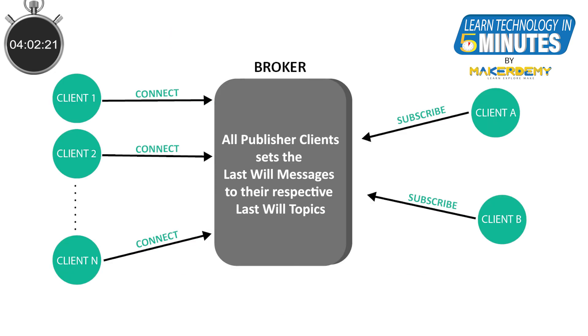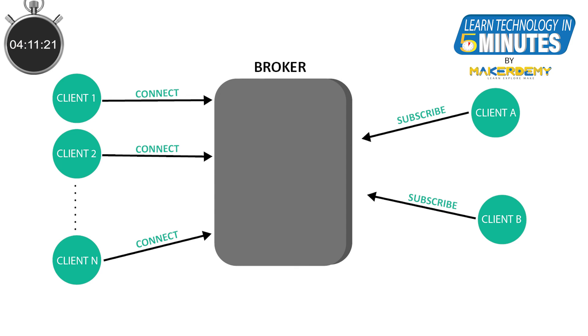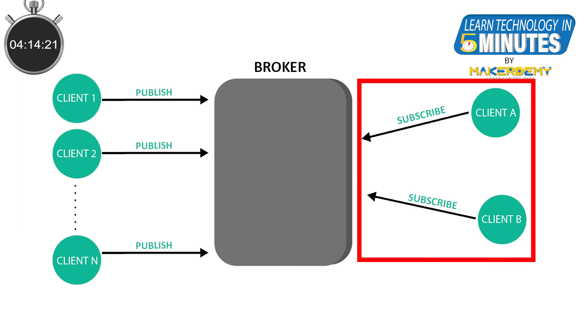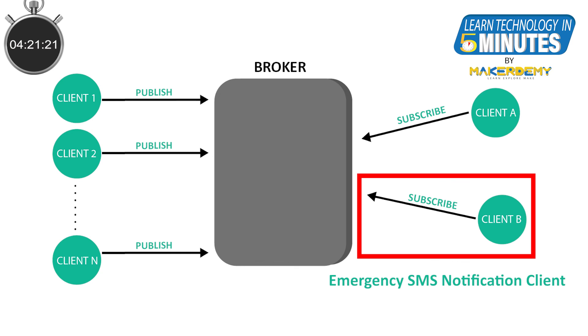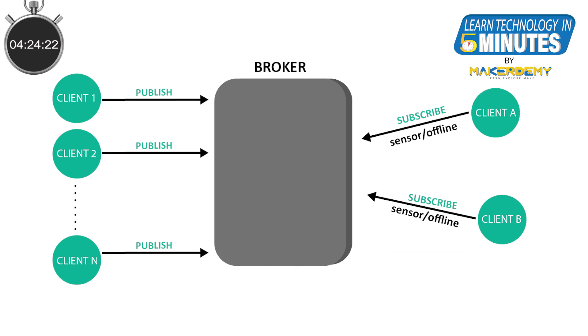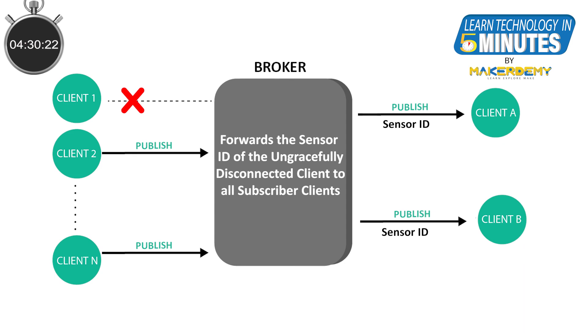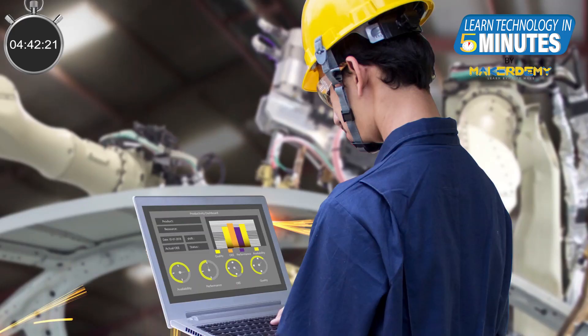This issue could have been easily solved if the system had used the Last Will and Testament feature of MQTT. All the sensor nodes, on their first connection to the broker, will set the last will message as their sensor ID to a topic called sensor/offline. Let's say we have two subscriber clients: one for the HVAC control dashboard in the factory and another is an emergency SMS notification client. Both clients are subscribed to the same last will message topic. Now when a sensor disconnects ungracefully, the broker will forward the sensor ID of the specific node to both clients. One client will show the details on the dashboard while the other will send an SMS to the concerned staff. With the sensor ID information, technicians can easily find and replace or repair the specific sensor node.